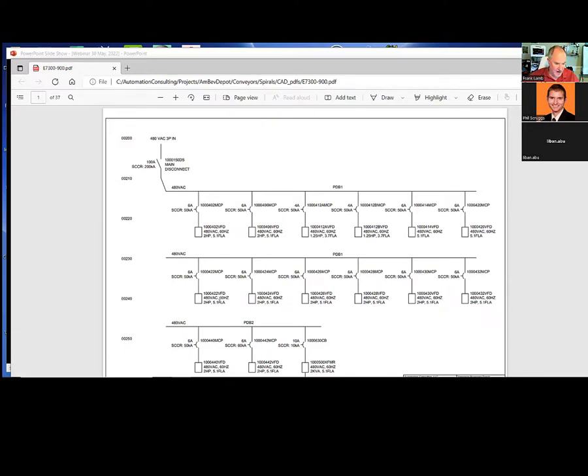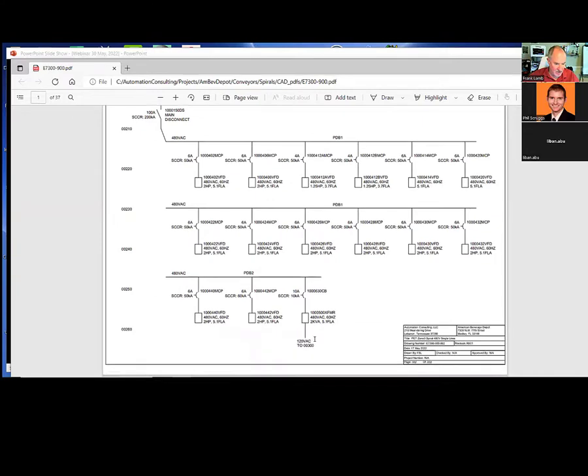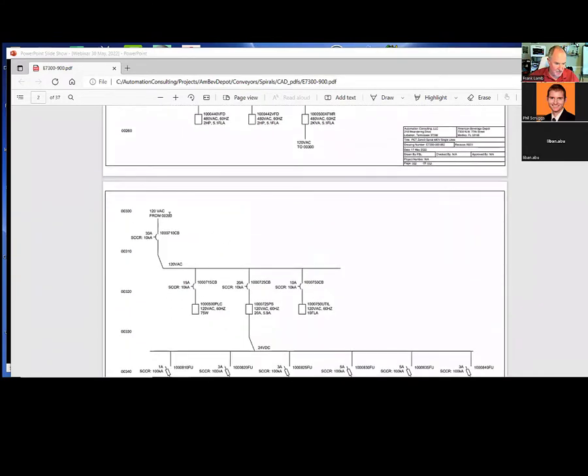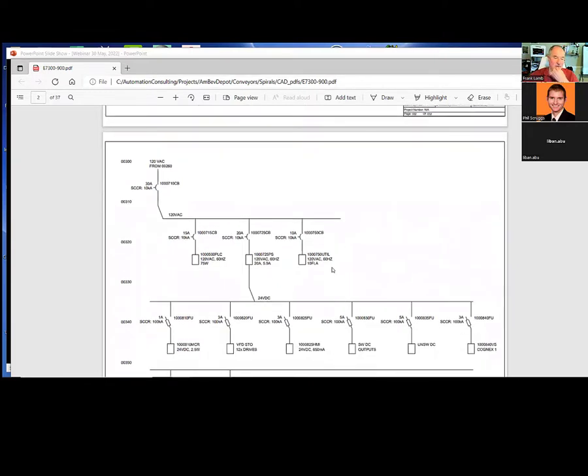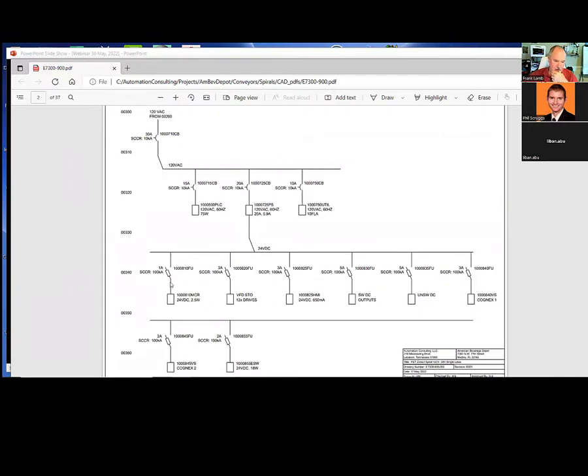This is all the 480 volt stuff. Then you get down to this transformer, and it transitions into 120 volt stuff. There's the PLC, a big 24 volt power supply, and a big utility outlet—I didn't even know what all would be attached to this, but probably things like plugging in your laptop, and the lighting for the vision systems will likely be on this outlet too. Everything else is pretty much 24 volts.